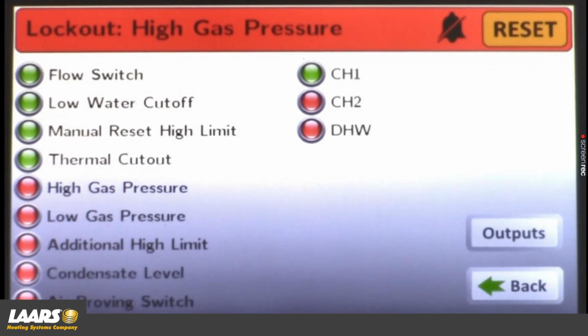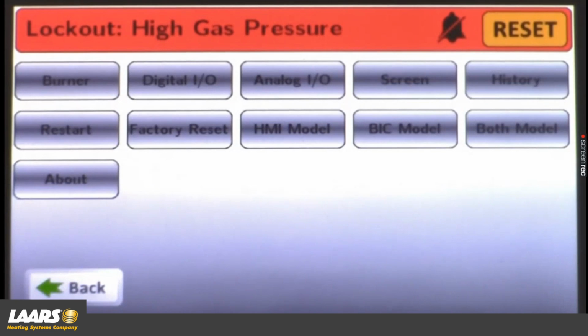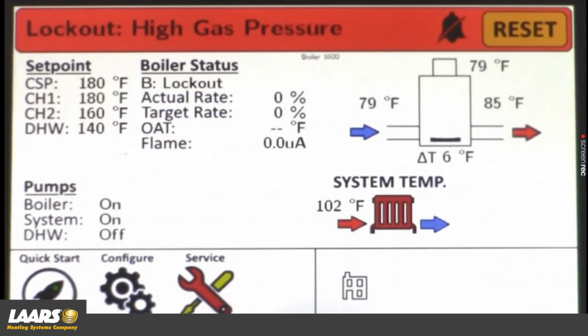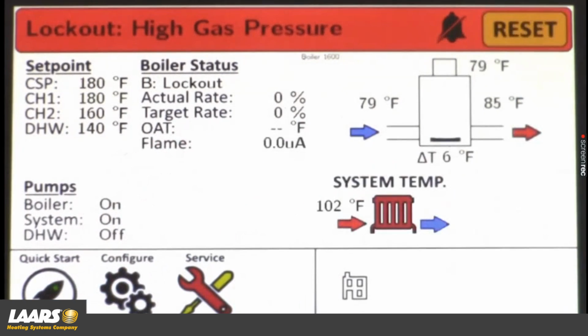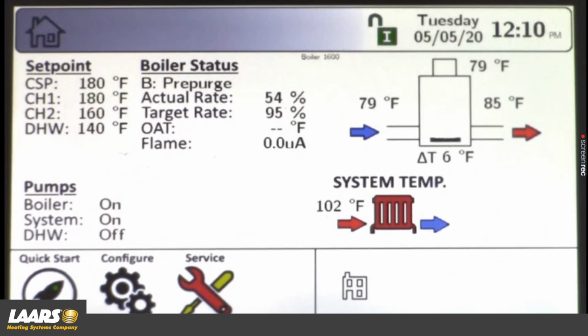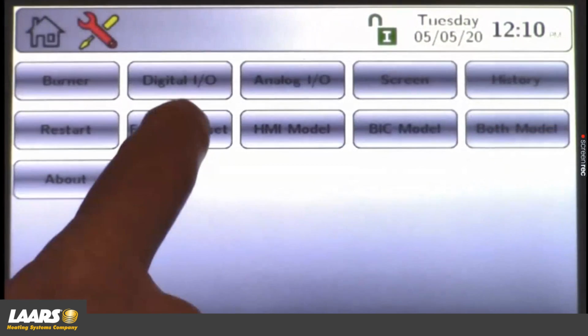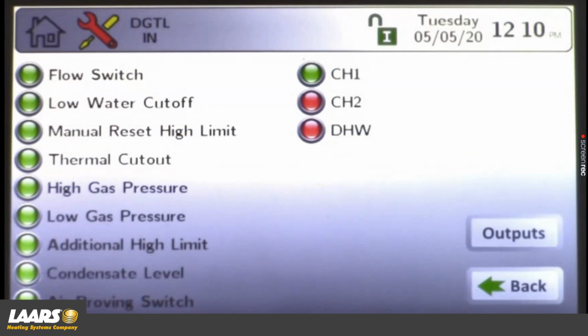So in this example, I'll reset the high gas pressure switch. However, I'm still in a hard lockout. And no matter what I do here, even if I go back to the home screen, it will be there. So once the device is reset and our blower is off, now you can reset from the home screen. So it'll be locked out in two areas. One is the device, and one is the actual home screen for Laars Link. So again, that's your sequence of operation.